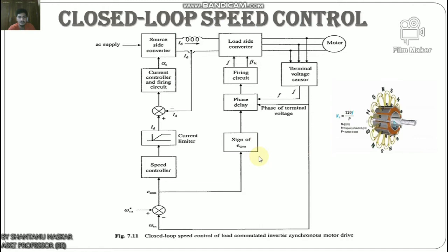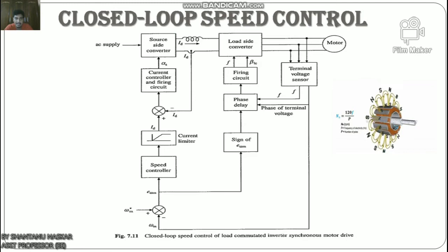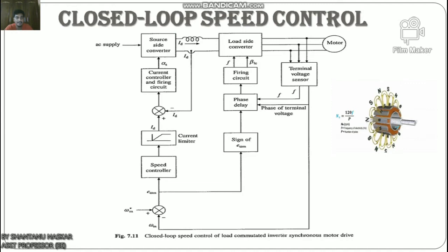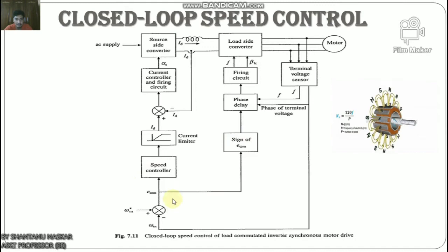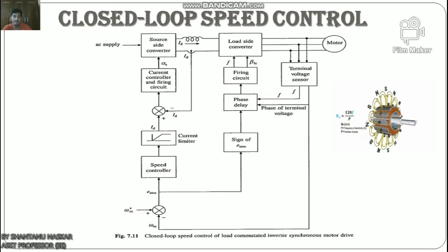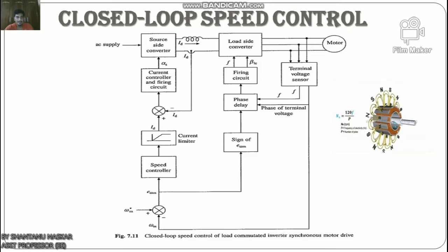Now we will discuss closed-loop speed control. The scheme employs an outer speed control loop and an inner current control loop with a limiter, similar to a DC motor. The terminal voltage sensor generates reference pulses of the same frequency as the machine induced voltage. The phase delay circuit shifts the reference pulses suitably to obtain control at a constant commutation lead angle βlc. Depending on the sign of the speed error, βlc is set to provide motoring or braking operation. An increase in reference speed ω*m produces a positive speed error; βlc is set for motoring operation, and the speed controller and current limiter set the DC link current reference at the maximum permissible value so the machine accelerates fast.